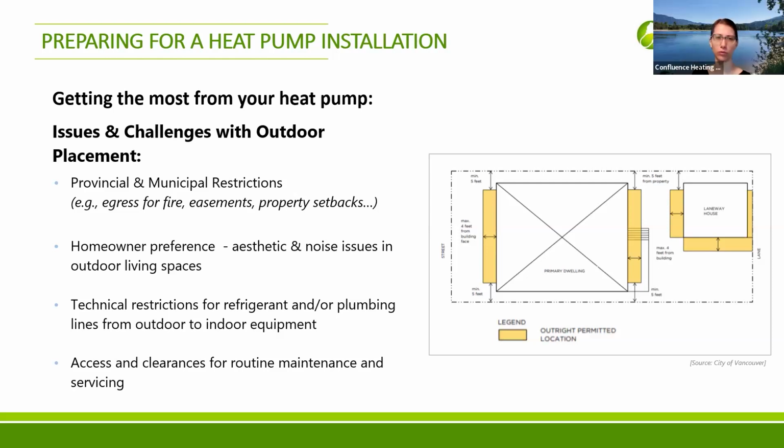Well, we have a job in Roslyn. It's a 3-story building, and they want to put in a ductless split. It was built at the ski hill, I don't know, 10 years ago or something. They want air conditioning now, but the one indoor head is going to be 60 feet away, 60 feet up. So that's the issue, that you've got a grade difference, an elevation difference. So we're just wondering about piping practices that you would recommend in this.